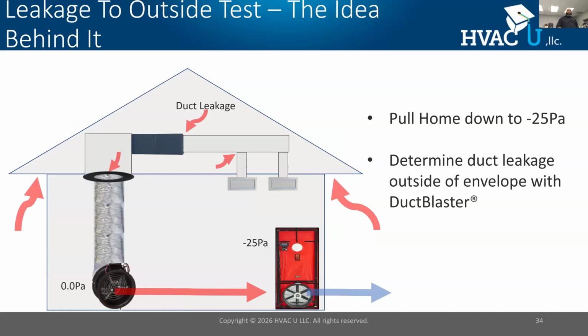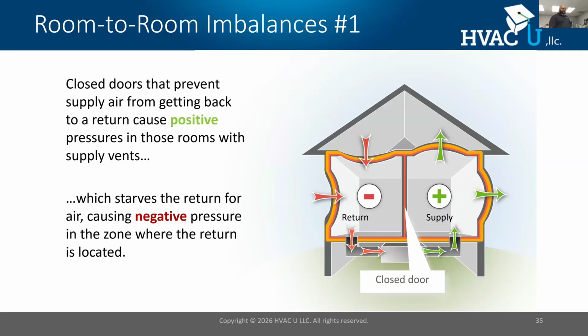All right, here's how it works. Again, I run a blower door and duct leakage tester. They need to be going the same direction. So if my blower door is in pressurized mode, my duct leakage tester needs to be in pressurized mode. I need the pressures to cancel out. As I'm moving air through the duct system, if it can't get into the house, it can only leak outside, and I'm going to quantify that. All right, our next duct evaluation.